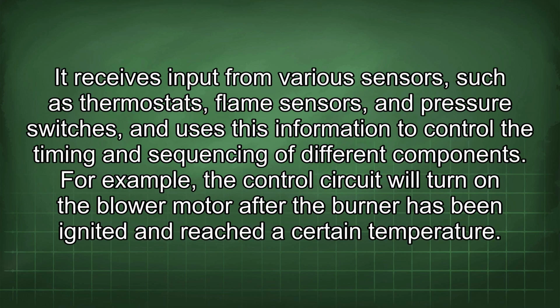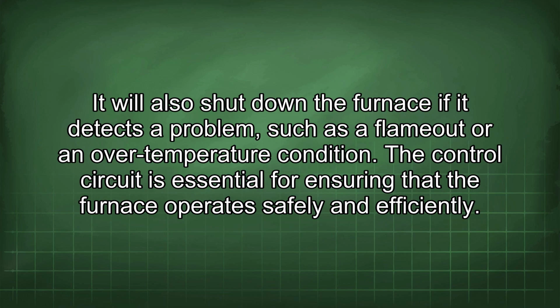It receives input from various sensors, such as thermostats, flame sensors, and pressure switches, and uses this information to control the timing and sequencing of different components. For example, the control circuit will turn on the blower motor after the burner has been ignited and reached a certain temperature. It will also shut down the furnace if it detects a problem, such as a flameout or an over-temperature condition. The control circuit is essential for ensuring that the furnace operates safely and efficiently.